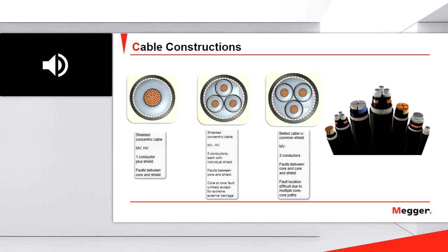If we have a fault, the fault would happen between the conductor and the individual concentric of each one of the phases. But the last one, the cable on the right, is different, because it is a three-phase cable with a common shield, a common concentric for the three phases. In this case, we can have a fault between the conductor and the common concentric, but also faults between the conductors, between each of the three phases.